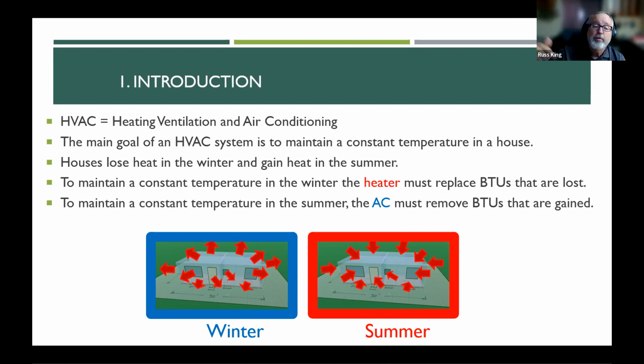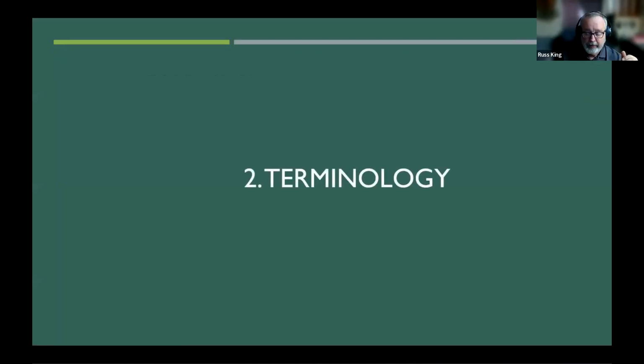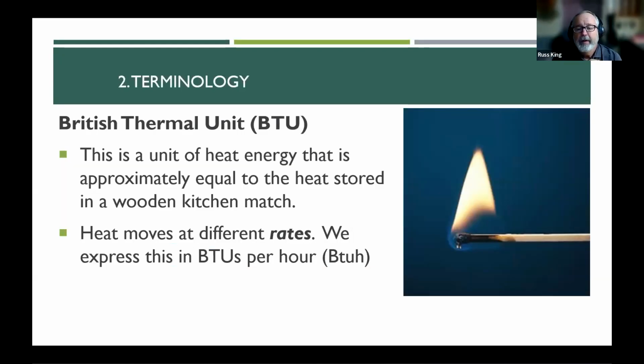Okay, BTUs come in through your windows. When the sun shines through your windows, those are BTUs coming in. When hot air leaks into your house, when heat conducts through the walls, those are BTUs coming into the house, and you have to remove those BTUs, okay? And when you remove the BTUs from the air, you make the air cold, and then that cold air gets recycled back into your house. So you're not adding coldness, you're removing BTUs. So always think of it in terms of BTUs. That's very important, okay? All right, so some terminology.